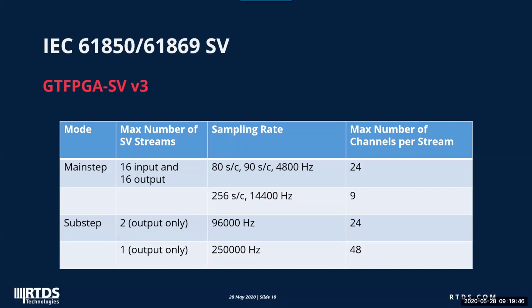The GT FPGA SV also supports a substep mode, which is for applications requiring even higher sample rates, such as 96K and 250 kilohertz. The IEC 61850 server and the routable features are only available on the GTNet X2 though.